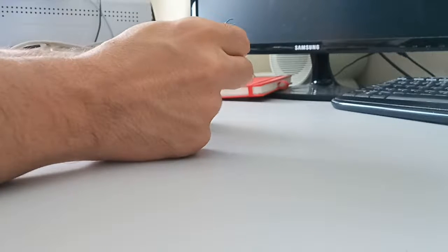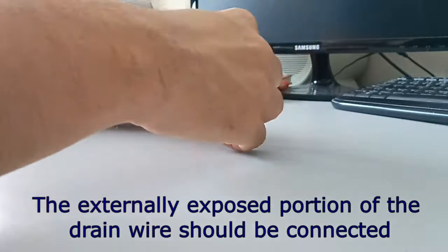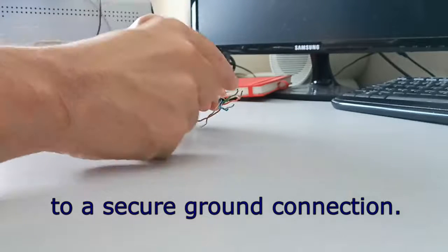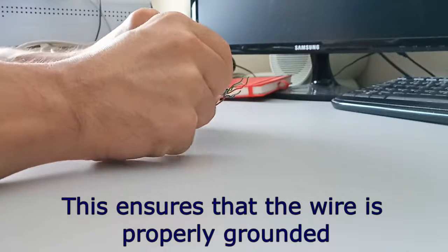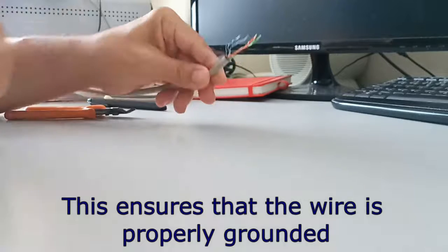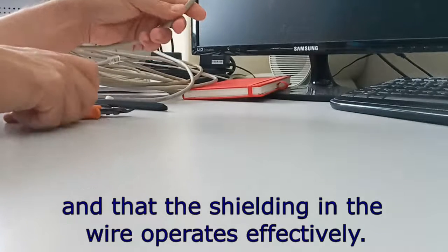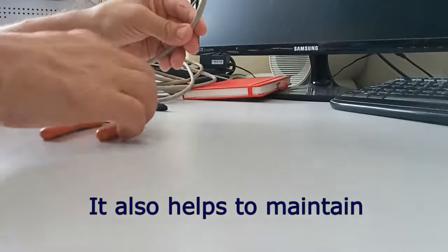The externally exposed portion of the drain wire should be connected to a secure ground connection. This ensures that the wire is properly grounded and that the shielding operates effectively. It also helps to maintain the two ends of the wire at the same voltage with respect to ground.